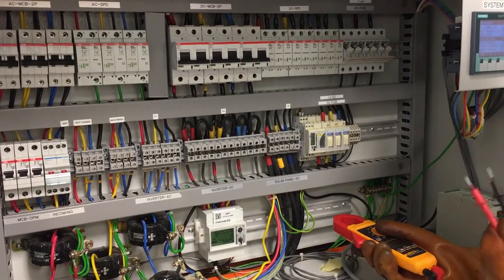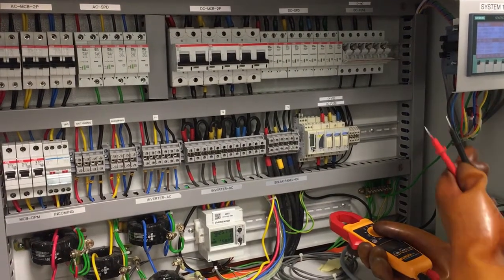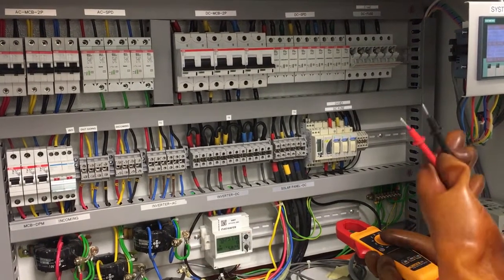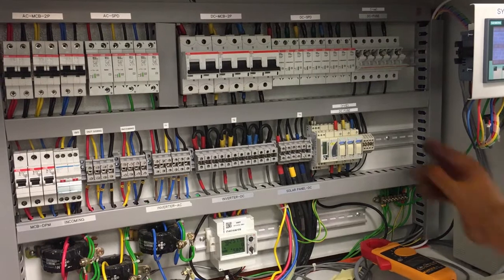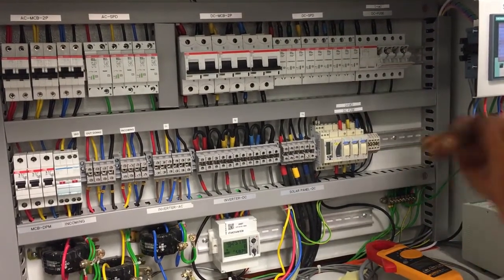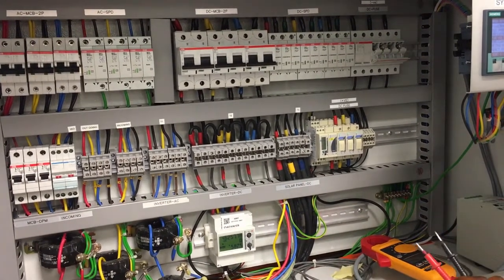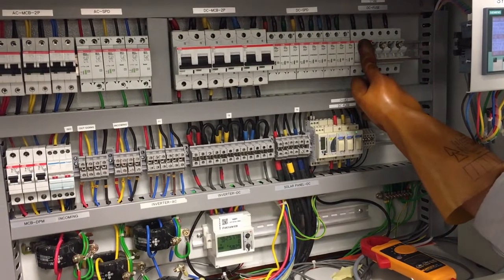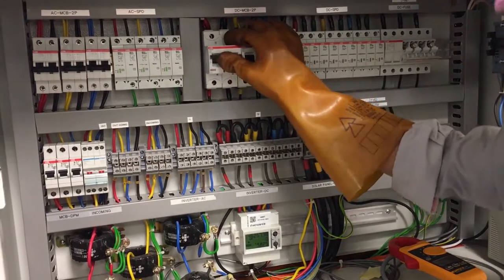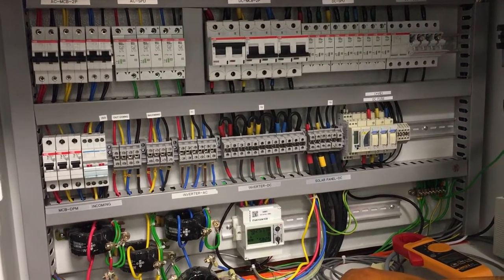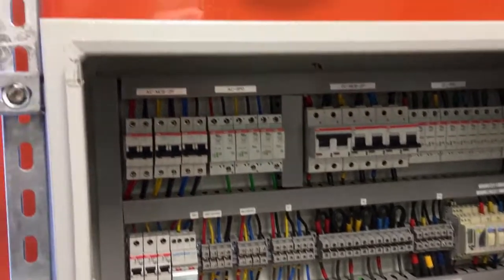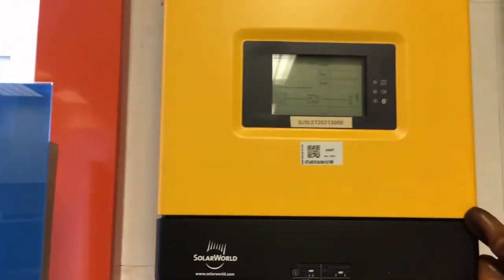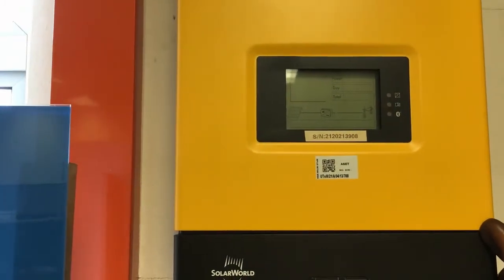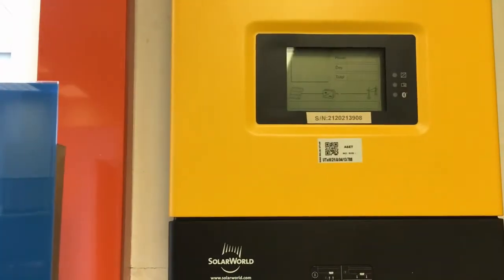Okay, so the sequence or the step to turn on, we always start from DC to AC. Okay, so turning on, we start from DC to AC. So now I will put in the DC fuses. I'm just going to do for one phase, so I'm just going to do for the left side. So I turn on the DC fuse, and then I turn on the DC MCB. Okay, so after I turn on, if you look at the inverter, after some time it should start. So there will be some delay, I believe. Okay, now the indicator light is blinking.